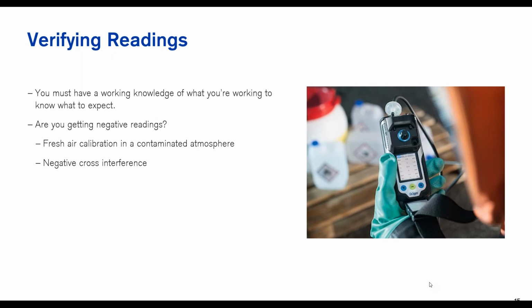Engage other team members to determine the relevant activities in your area. If you have 2 monitors next to each other, use those, but understand you may have 2 different readings, just depending on the technology of the meter you're using. If you're using a catalytic bead sensor versus an infrared, versus some other kind of technology, it may give 3 completely different readings, and understanding why that's taking place, which one is accurate, and how do you verify that it's accurate.